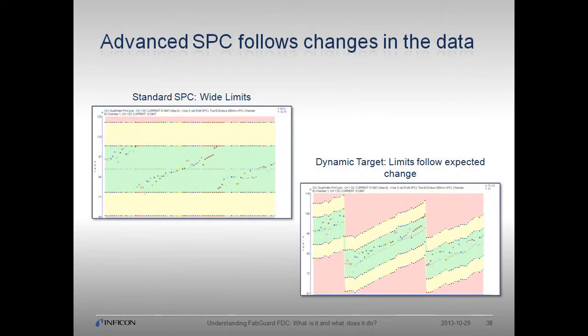FabGuard implements and extends traditional SPC to include dynamic target. In this example, standard SPC limits are insufficient to determine fault in data that is linearly related. Some variables are expected to change within a PM cycle, and FabGuard can use dynamic target to shape the SPC limits to the data and provide tighter control.